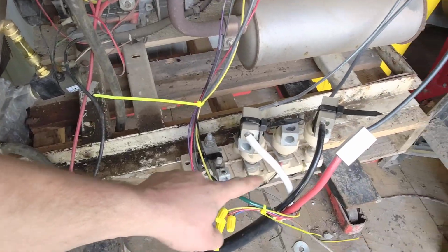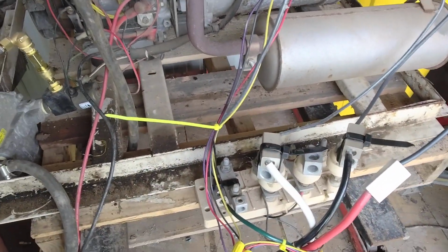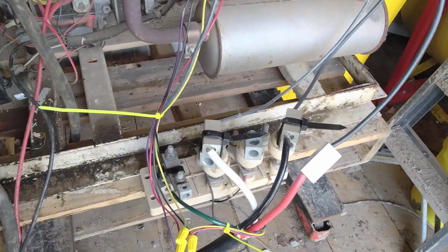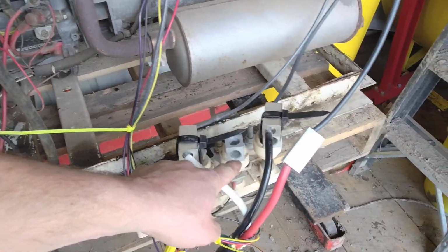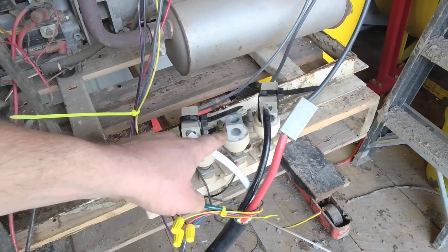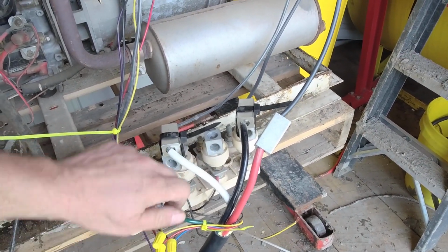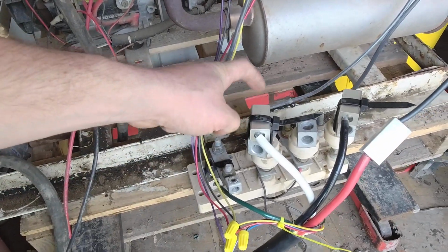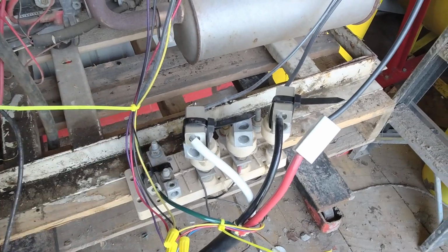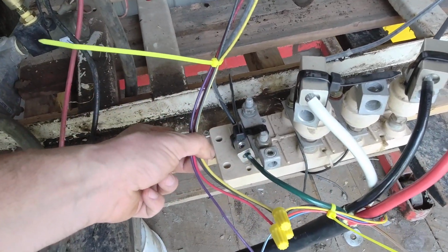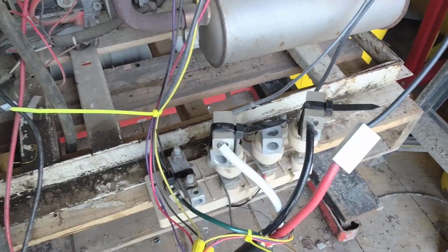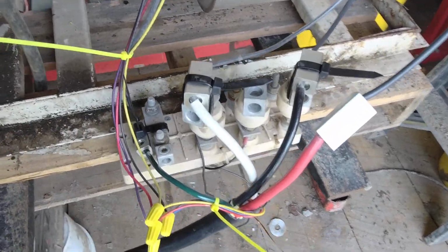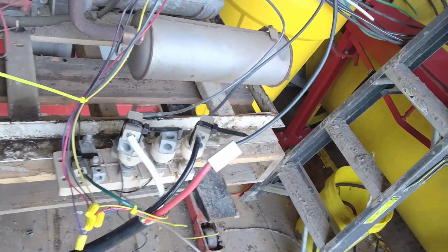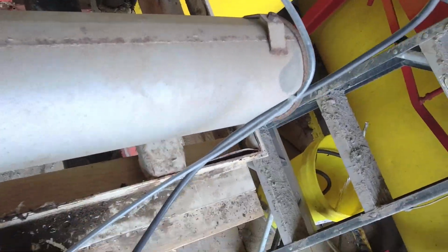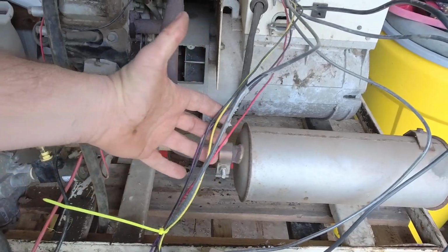You may remember this terminal block that was laying on the floor inside the gen shed. We're using that as a temporary connection. I was going to use the original lugs, but apparently when these aluminum fittings get corroded and you try to back them out with the Allen wrench, they strip themselves. So I had to run to Lowe's and get these splice blocks. I got one down on ground, our neutral and two hots zip tied in there so nothing touches. They're all insulated from each other, so we should be good to go. There's a little air gap between those and the muffler. This is all connected.